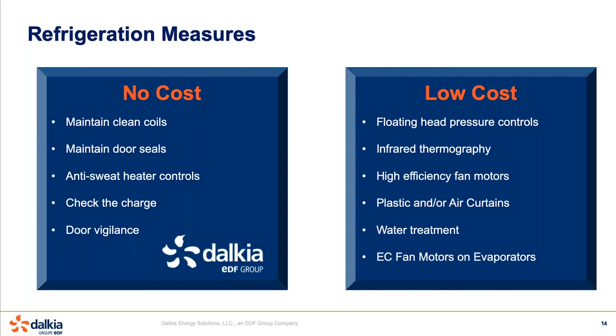All the compressors dropped right off, moving them a long way in terms of efficiency. On the low cost side, we want to leverage floating head pressure, evaluate with infrared to make sure thermal energy is going where we want it to go, look at high efficiency fan motors and EC motors, and consider adding plastic or air curtains to keep the cool space cool and the heat out. There are a lot of different potential measures between no cost and low cost.